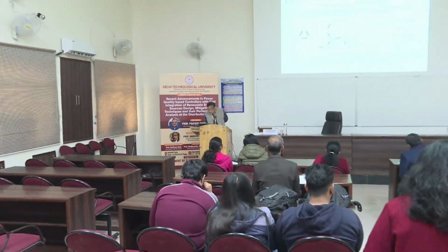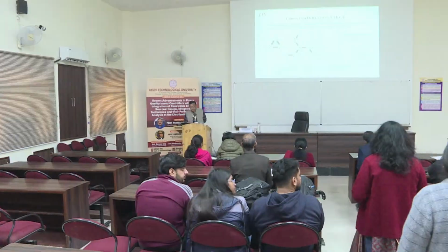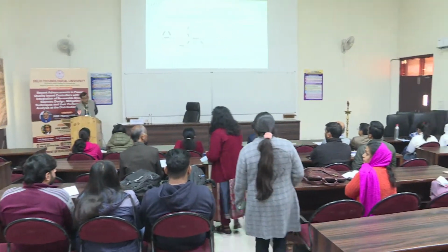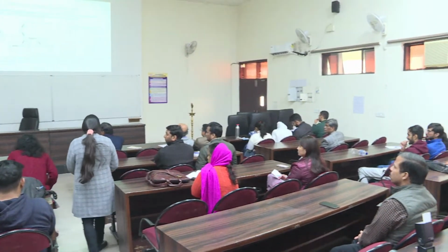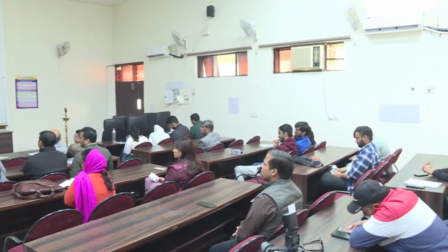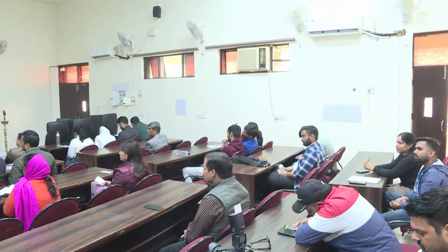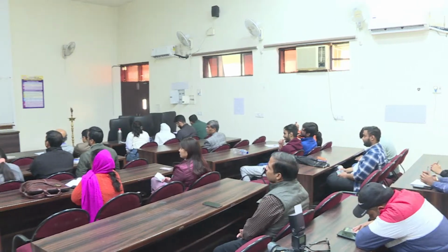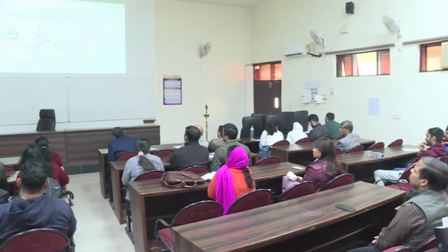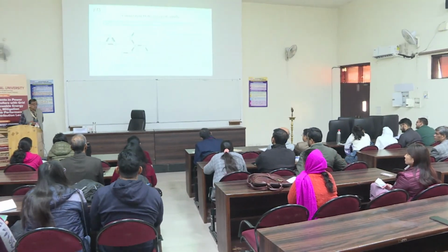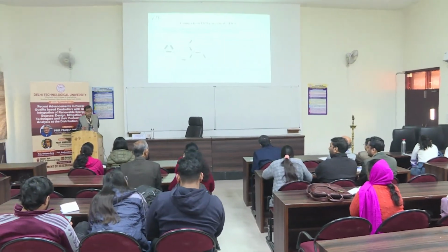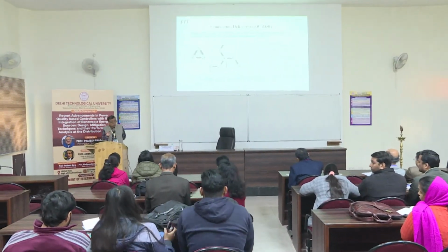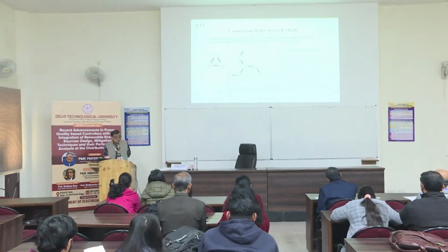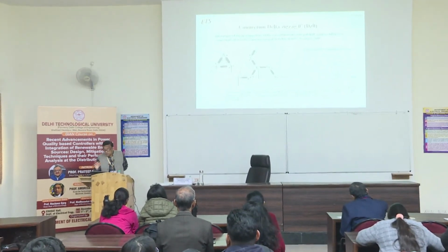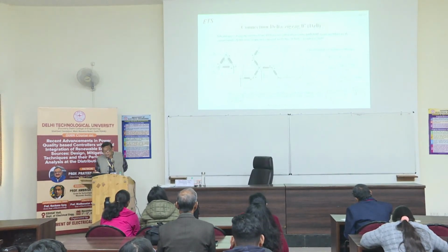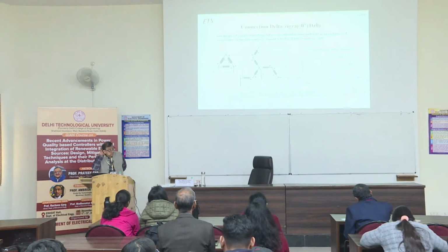But you have to see the advantages of zigzag. Advantage of zigzag we have already seen earlier. No core saturation even with half-wave rectifier or DC component. So this is the advantage of zigzag connection. On the secondary side, if you have a zigzag connection, then your core will not be saturated, because there is no third harmonic.